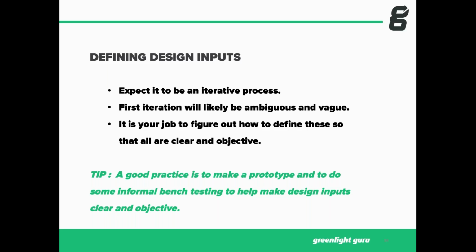That's the whole point, to use your design inputs as a scratch pad as you start to define what's important about this product, and use this as a guide to help you determine where you need to focus time, effort, and energy. Another thing to consider as part of the continual process of defining design inputs is to really understand that there are potential risks of your product. What could go wrong. We don't like to think of negative things, of course, but factoring risk management into this process early will help shape the design and development of your product as well.